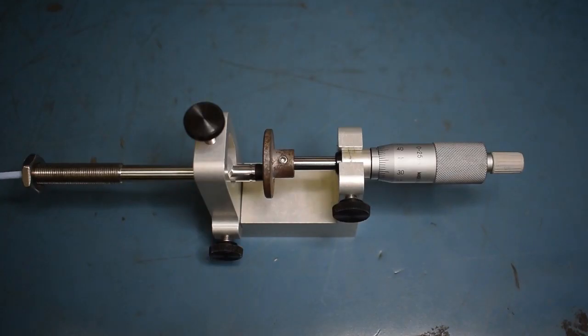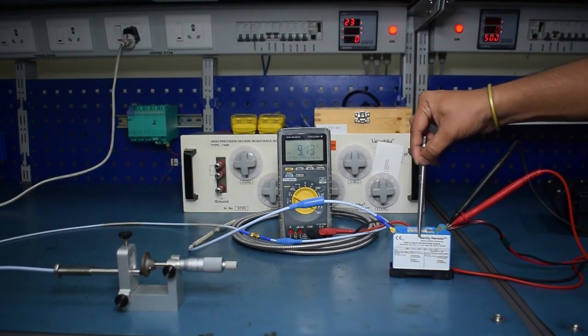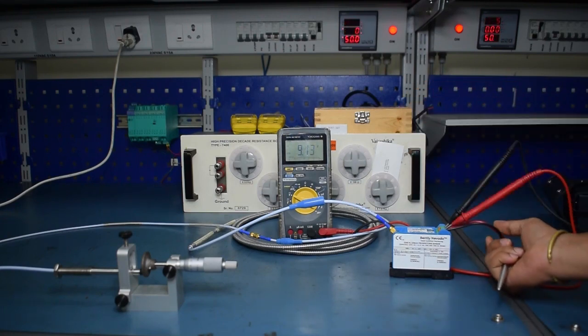The probe has to be mounted in the micrometer, and the probe has to be connected to the proximeter through an extension cable. Power up the proximeter by 24 volt DC supply.